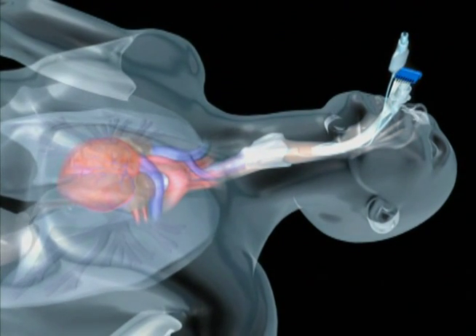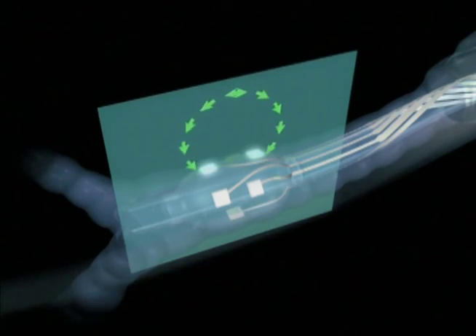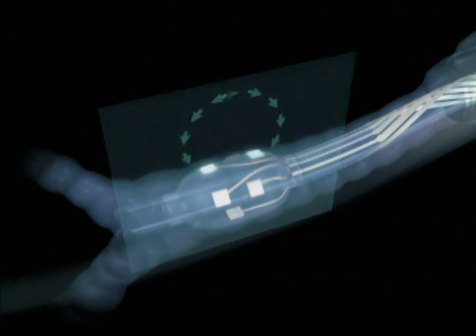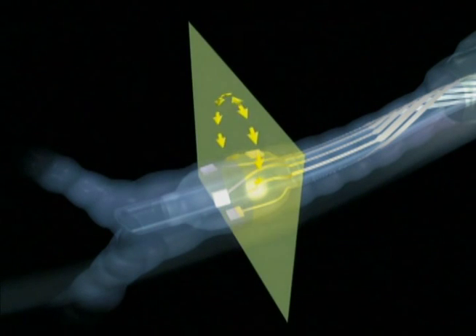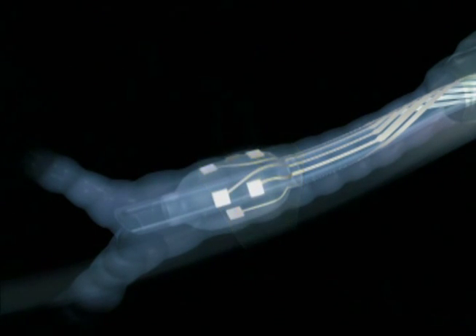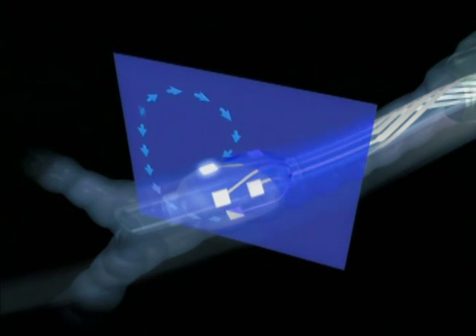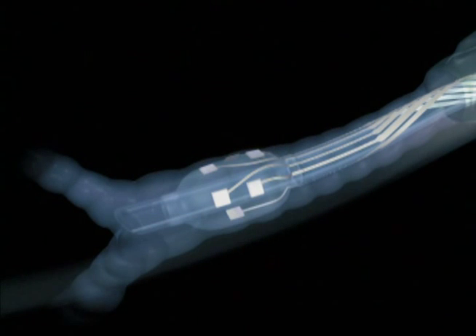obtain a usable signal. ECOM differs from other external impedance technologies by placing the sensor array internal to the patient in close proximity to the ascending aorta. The resulting internal impedance cardiography creates a small, focused electrical field to detect a large signal, as opposed to external impedance systems that use a large electrical field to detect a small signal.